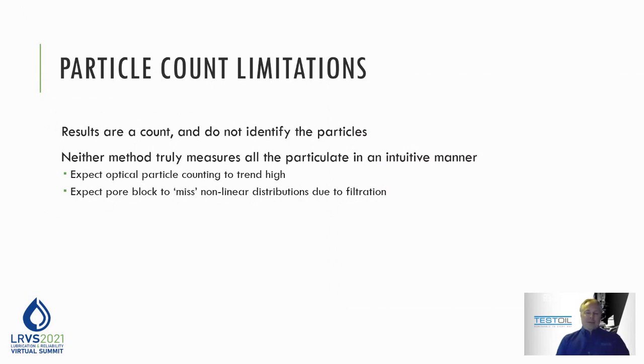But the other big takeaway is that neither method is truly measuring every individual particle and giving you a true physical dimension of that particle. It's essentially relying on one method or the other, either spherical equivalency or just physical screen size at one particular micron rating. The other takeaway is that you should expect optical particle counting to skew higher than the reality, which generally works in your favor, because if you can hit your target with a result that's skewed high, you're actually doing better than that.